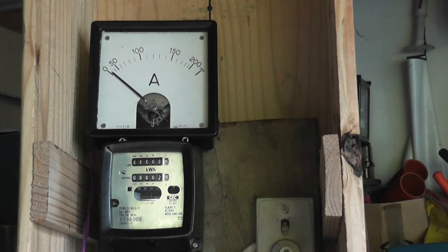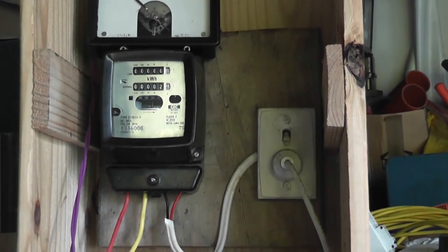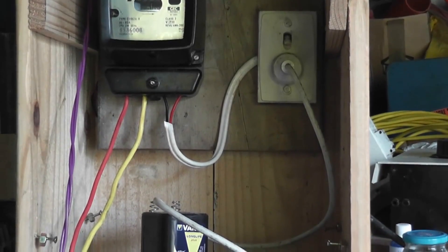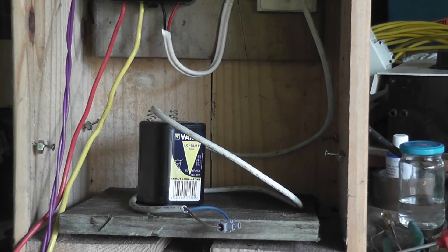Just set up. I'm going to overload a 7.5 amp lead on a 10 amp power point. 200 amp meter, kilowatt hour meter, 10 amp old New Zealand power board PDL60, and a lead which I've shorted out and hopped up to a phantom load transformer.